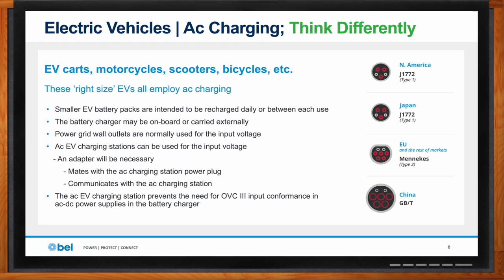Temperature may also be an issue for some of these chargers. If it's a bicycle charger, it may be inside your house, apartment, or office, so it's not such an issue. If it's a cart, it may be sitting outside in the cold or heat, so temperature extremes may be there. On level one and level two chargers, OVC3 input surge protection probably isn't an issue, because they're always considered downstream from either a level one or two AC charger, or they plug into the wall—they're not permanently wired there.